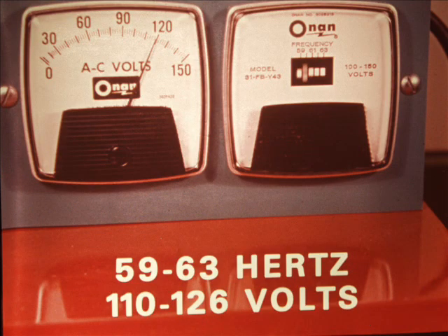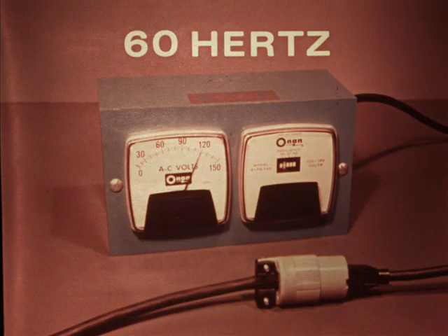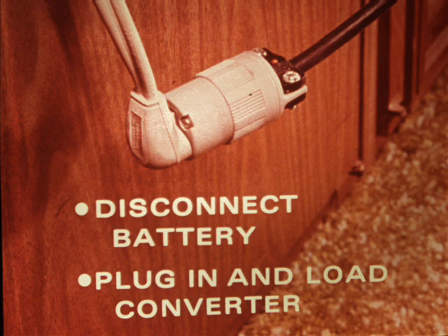Also, check the frequency of the 120-volt input. Testing at the motor generator output terminal, the frequency meter should read 59 to 63 Hertz at 110 to 126 volts. If the frequency is less than 60 Hertz, the converter output voltage starts to fall off. Also, when testing the converter with shop power, plug in your frequency meter and be sure your source is 60 Hertz or more.